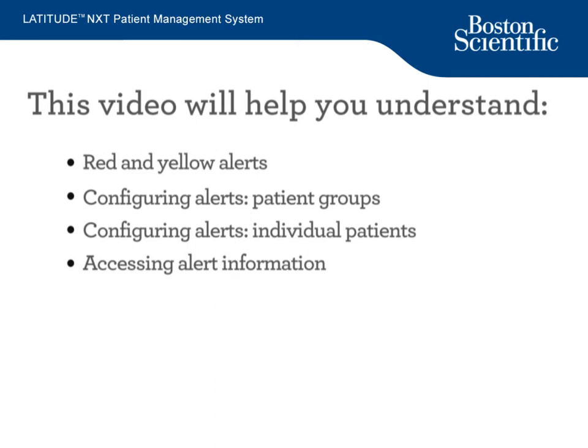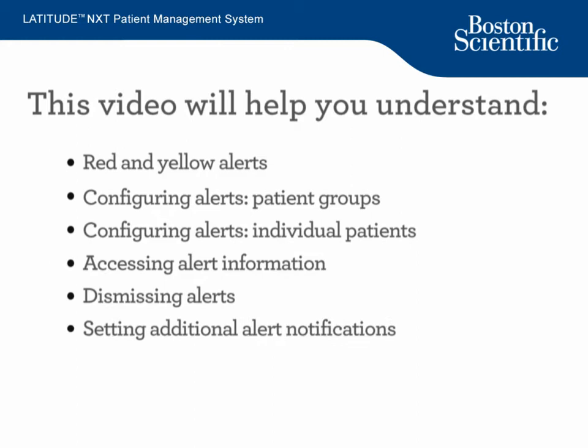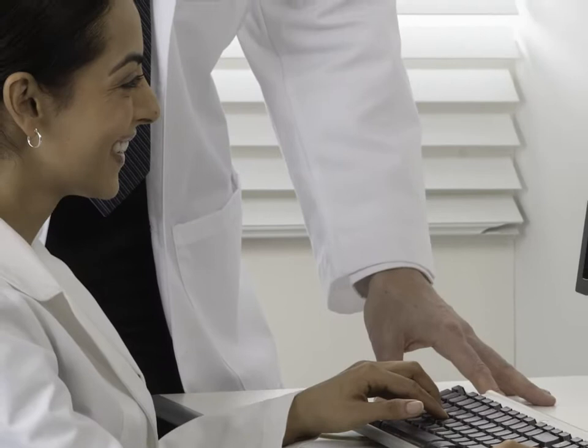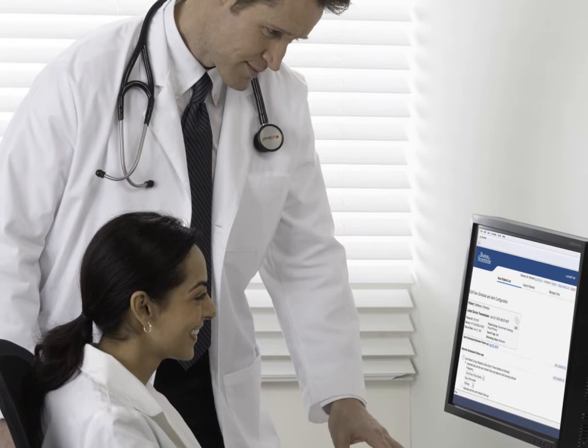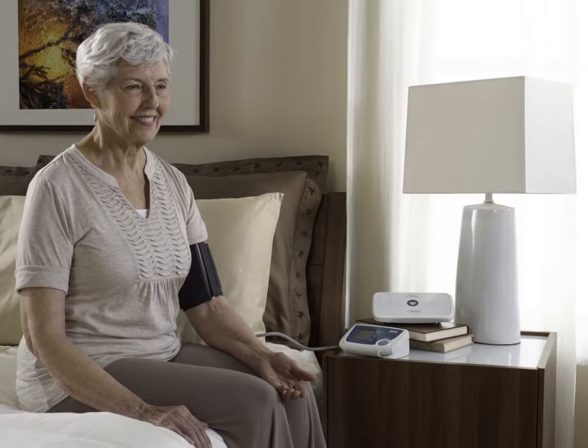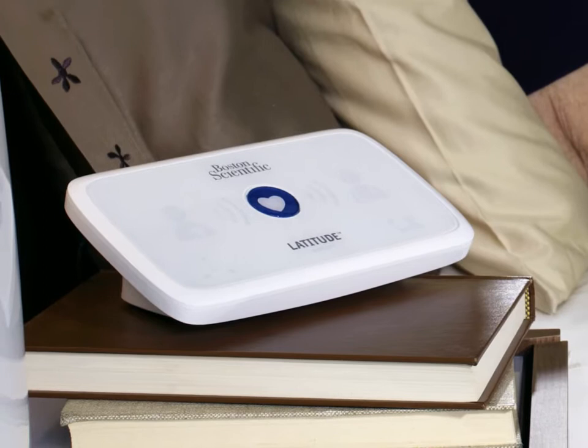We'll start by covering the basics of red and yellow alerts in Latitude Next. Alert monitoring provides additional device and patient health status monitoring between scheduled follow-ups, which is designed to help you see changes sooner. In addition, Latitude Next conveniently allows you to configure your alerts without bringing your patients into the clinic. Alert notifications are generated for a number of conditions which vary depending on the implanted device model. There are two levels of alert conditions: red alerts and yellow alerts.